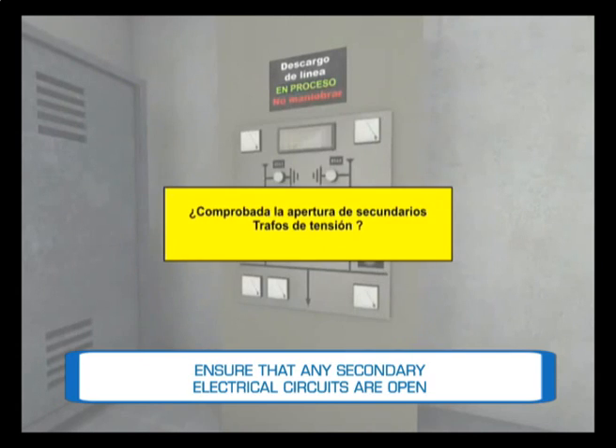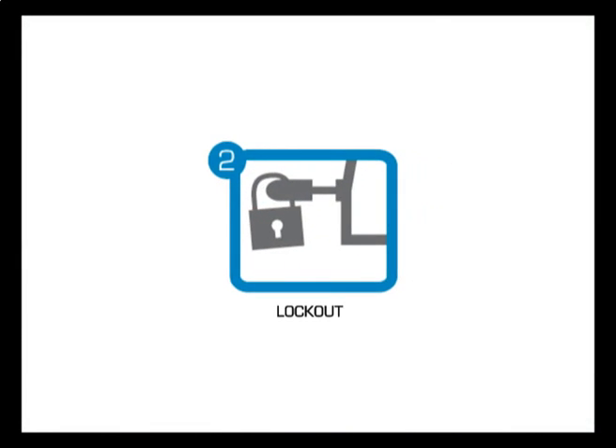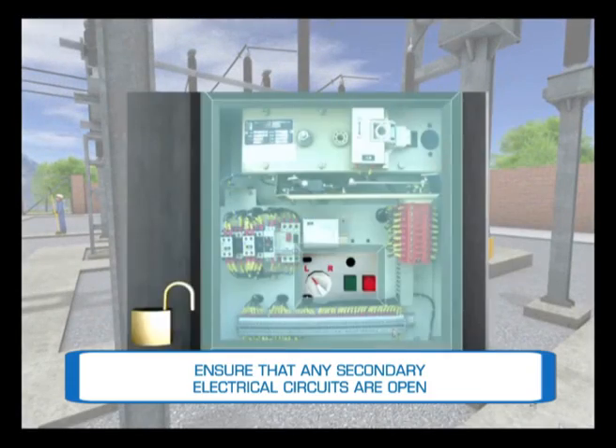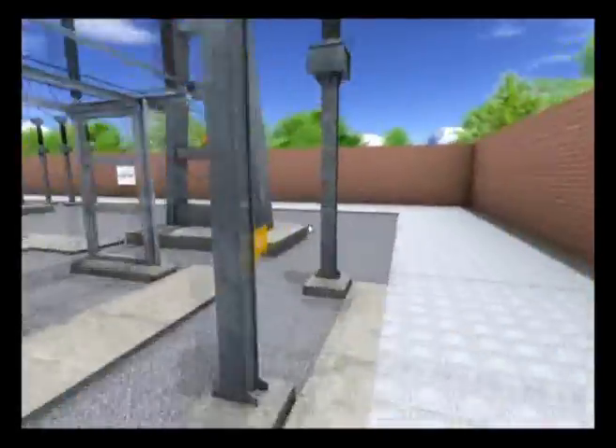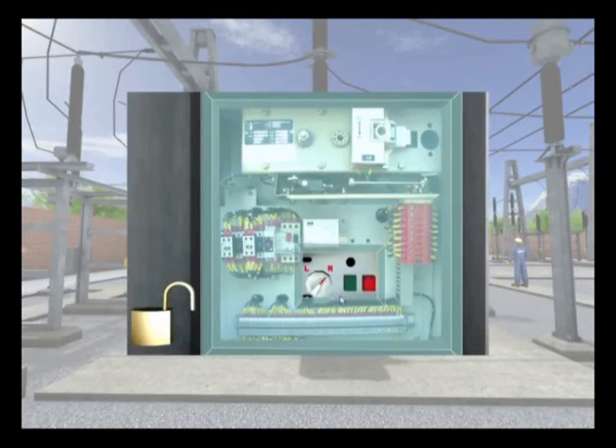The worker must isolate the part of the installation where work is to be carried out from all power supplies. The second golden rule: lockout. The worker must secure the installation against any possible reconnection, preferably via mechanical lockout.